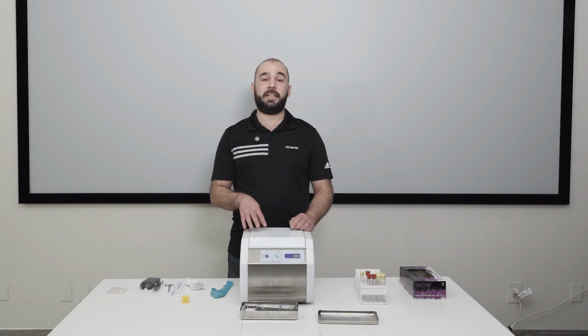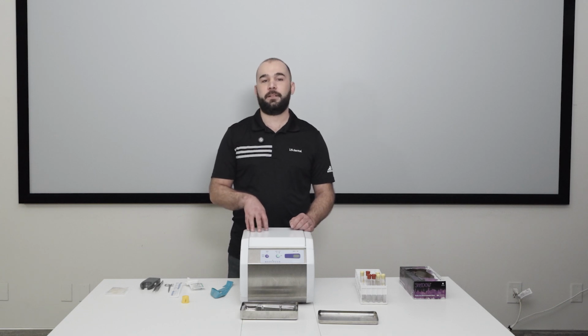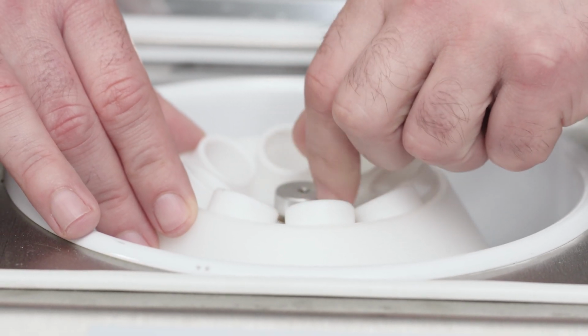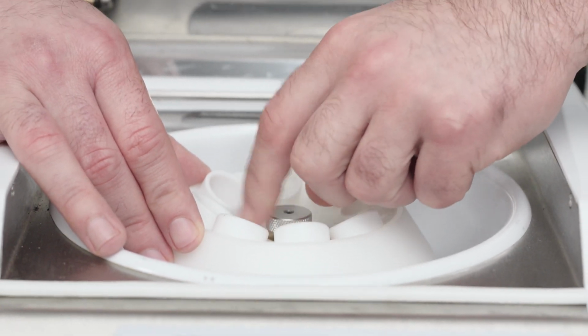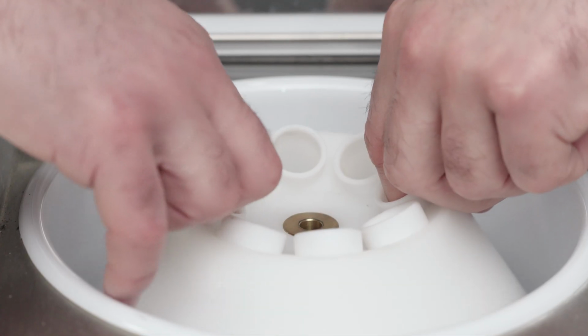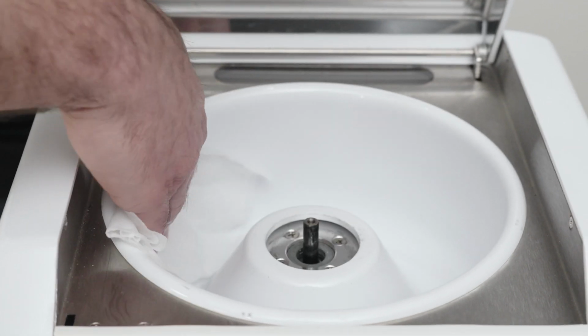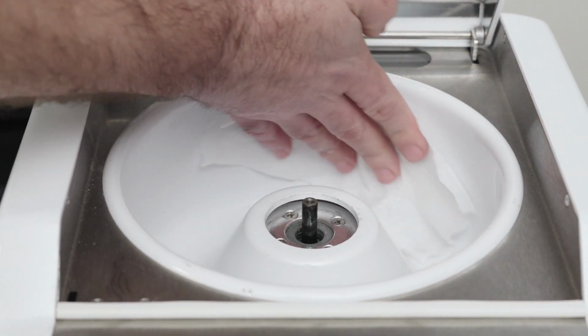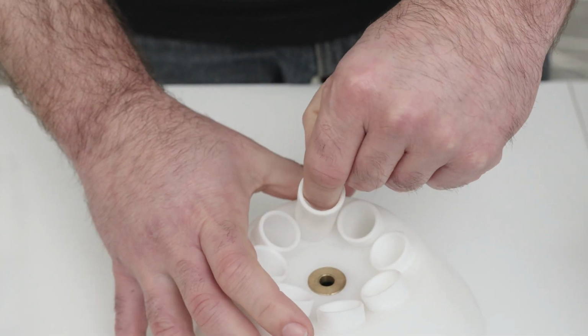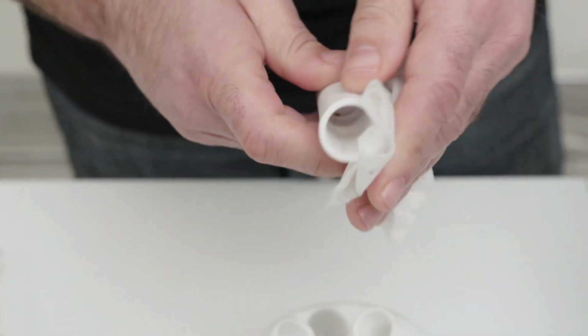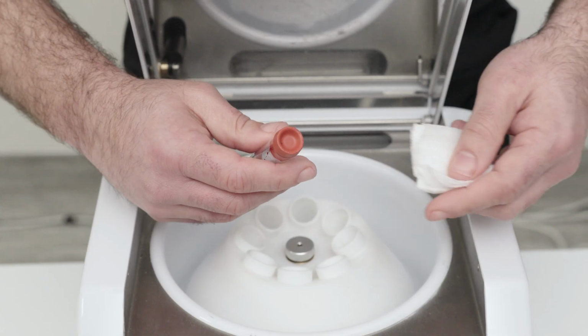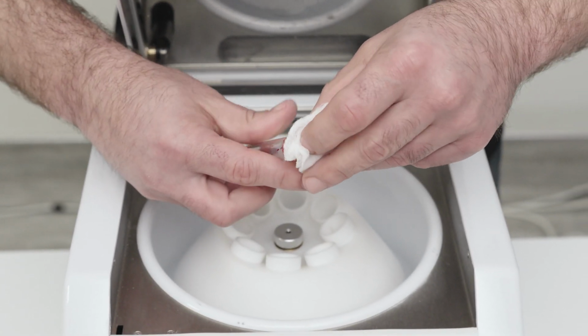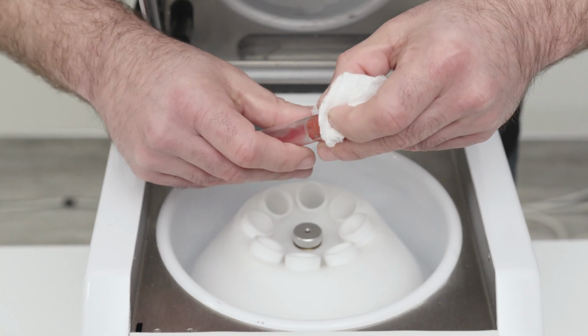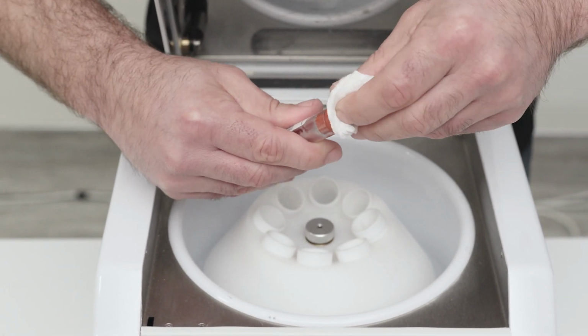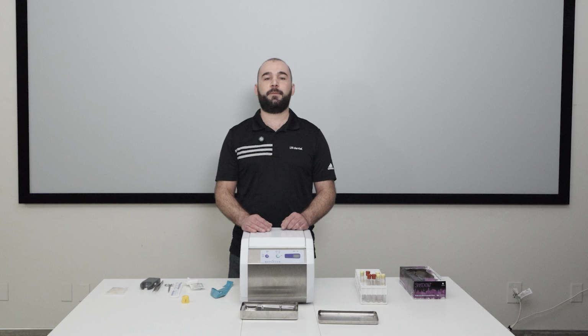Regarding the internal cleaning and maintenance of the machine, there's a metal screw in the center of the rotor. Turn it counterclockwise to remove the rotor and clean it with CaviWipes or mild alcohol. The tube holders can also be removed for cleaning. Here's a quick tip. Always use the gauze or a piece of paper to wipe off the top of the caps after drawing blood. This will save you time on cleaning and prevent the machine from getting dirty quickly.